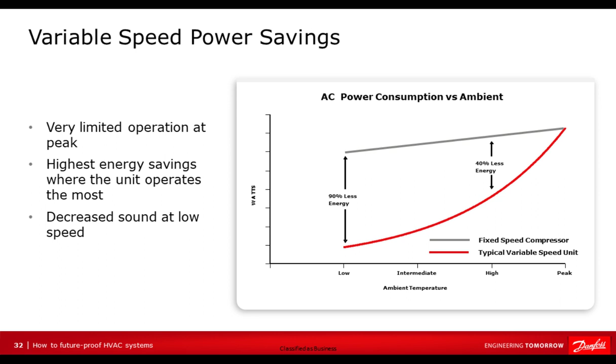Variable speed also offers power savings. With variable speed, you can achieve the highest energy savings where the chiller operates most of the time, which is in that lower 30 to 70 to 80% range. By avoiding oversizing a system, the key benefits include reduced electricity bills, lower inrush current, and increased comfort and processes. By reducing the speed, we also decrease the sound versus the fixed speed compressor. Also, with the VFD, you get lower noise levels.